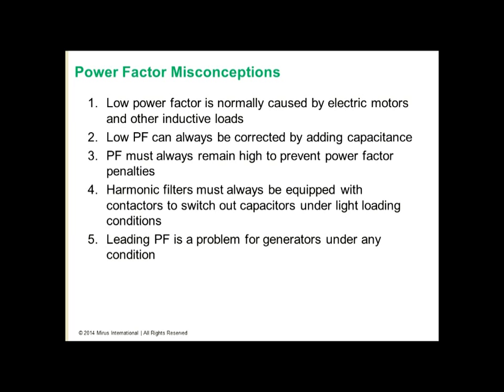The fifth is that leading power factor is a problem for generators under any condition. It is true that a leading power factor that results in high levels of capacitive reactive power is a problem for synchronous generators, but in certain conditions, power factor can be low and leading without there being too much capacitive reactive power for the generator.